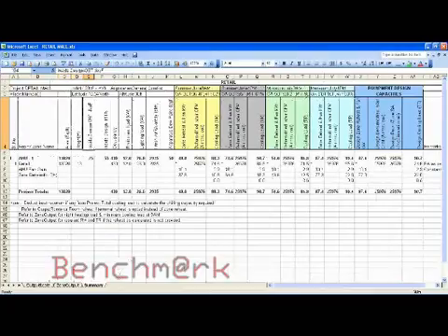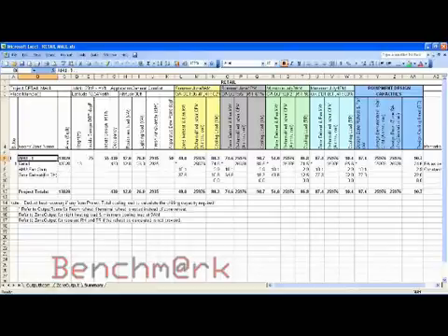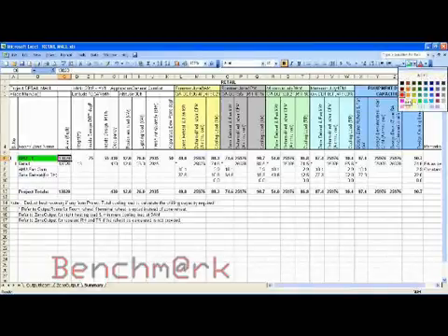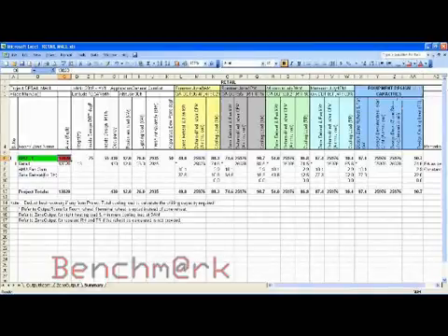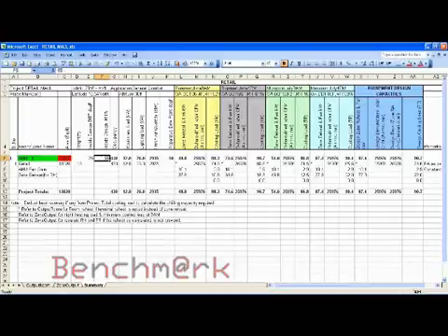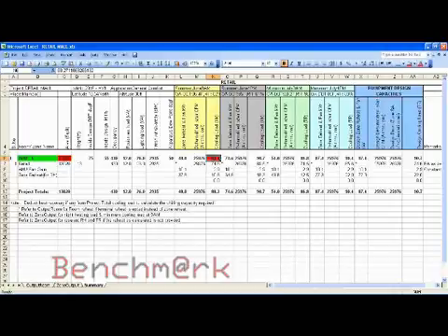This is the project summary for all data entered, including latitude, altitude, area, volume, occupancy, lighting load, equipment load, and fresh air load. For summer, monsoon, and winter at 4 PM and 9 AM, we are also getting equipment capacities like CFM, tonnage, and reheat. For this project we can see reheat is required to maintain the conditions.